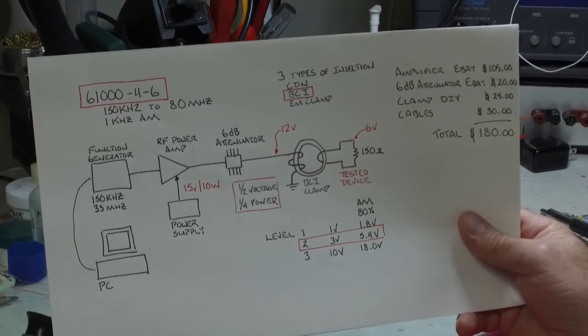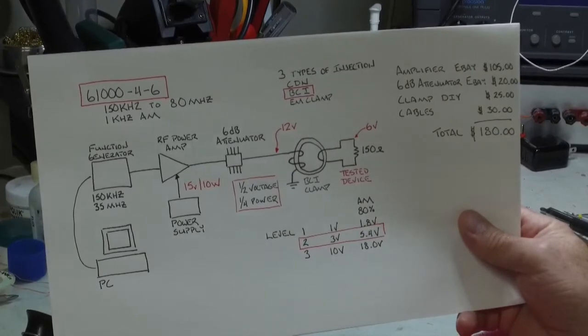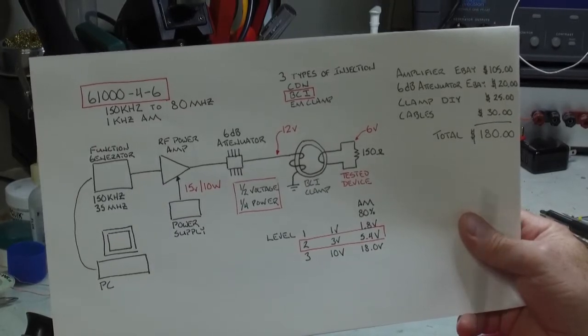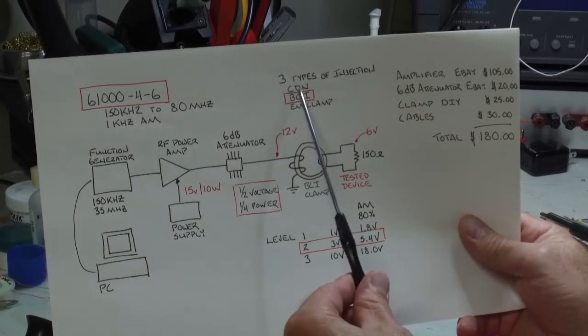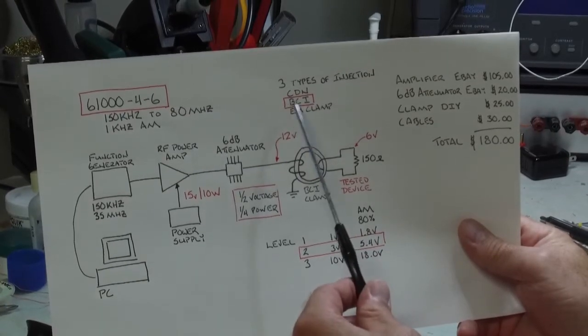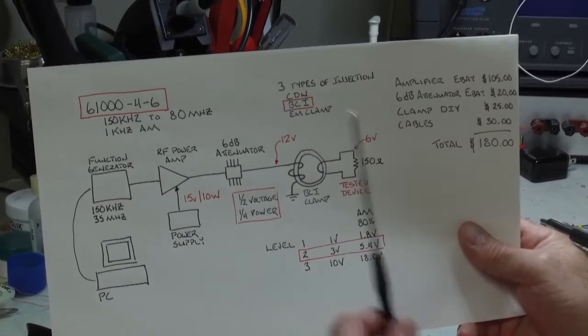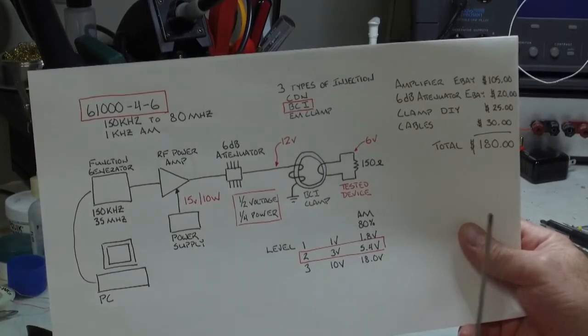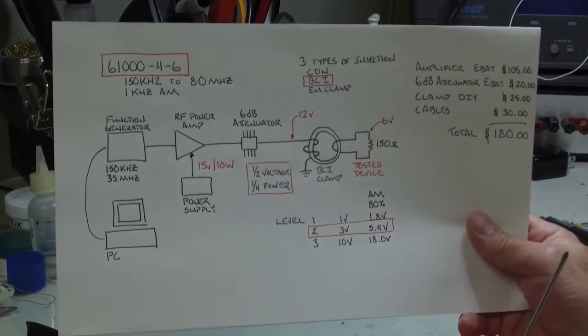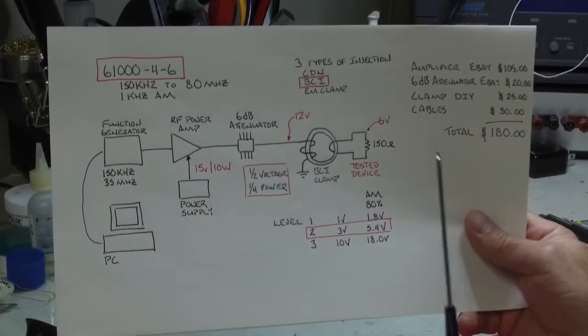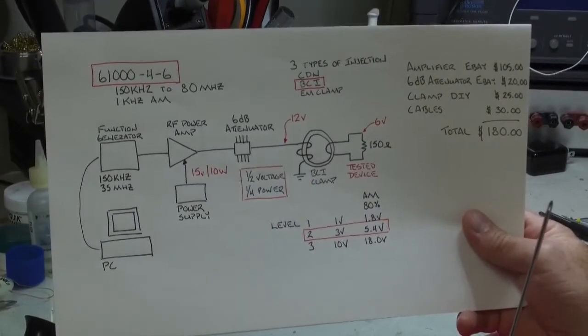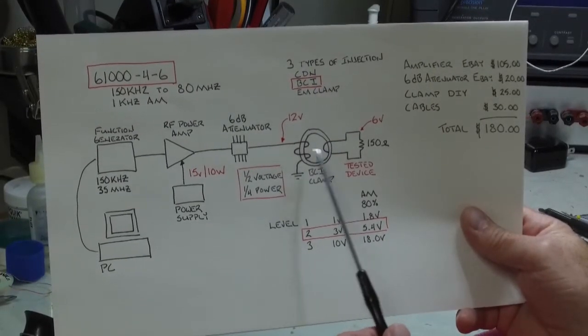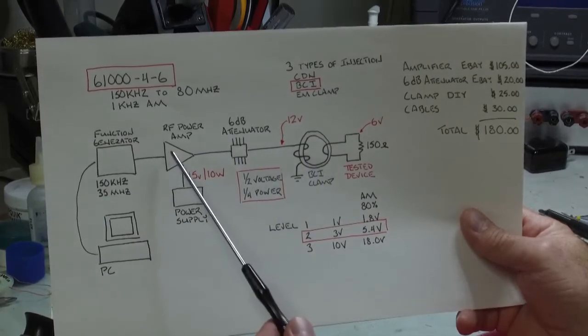I should note that there's three different types of ways of injecting this signal onto your system. There's a CDN, a coupling decoupling network, the bulk coupling system, and an EM clamp. I'm illustrating the bulk coupling because that to me is the easiest to use. It might not have the most repeatable results like a CDN, but it's easier and lower cost.